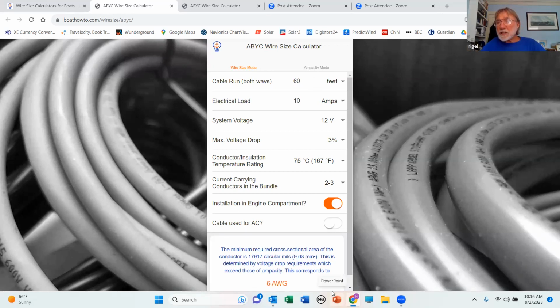Remember before, when we had a 60-foot run with a 10% volt drop, we needed a 12 gauge conductor. At 3% volt drop, we've gone to 6 gauge. Wow, that's amazing. That's double the diameter. It's 4 times the cross-sectional area. It's very expensive to wire to 3%. So go and use these tables.